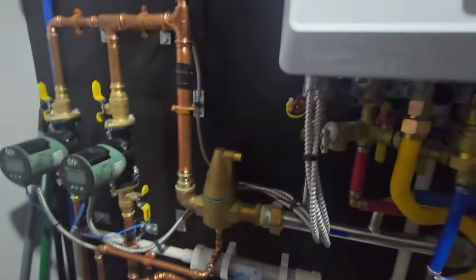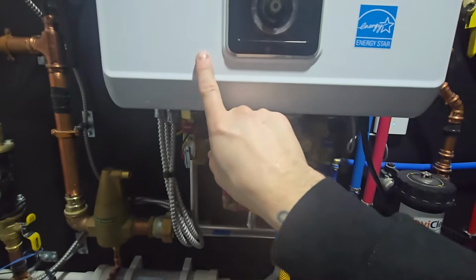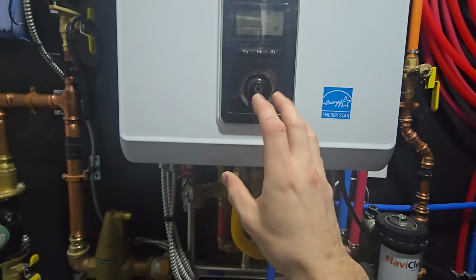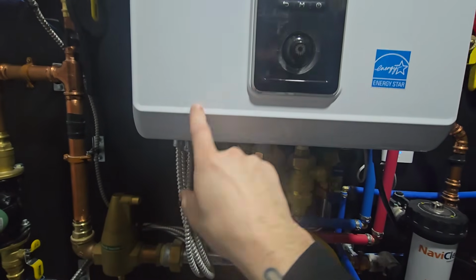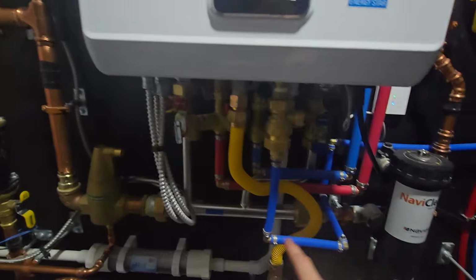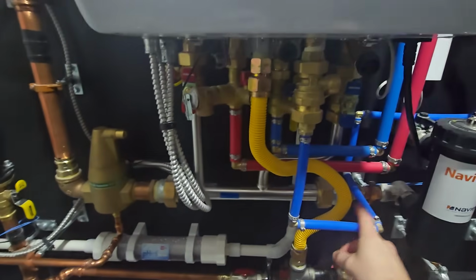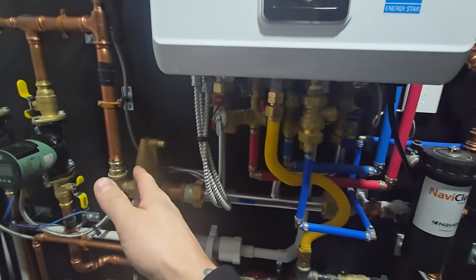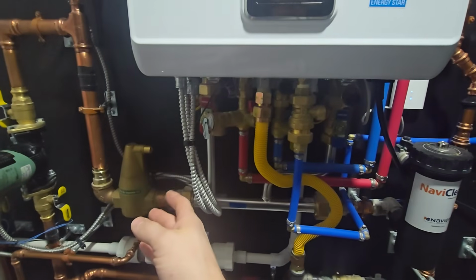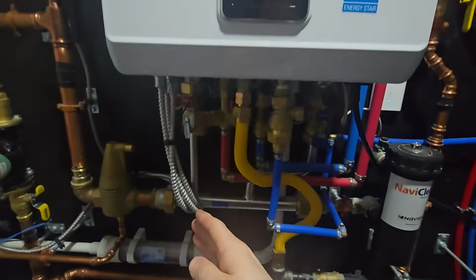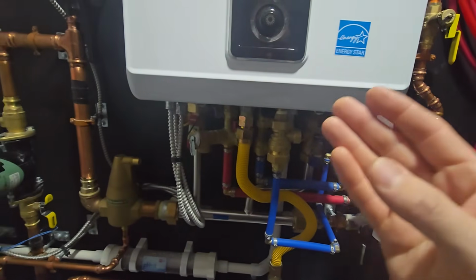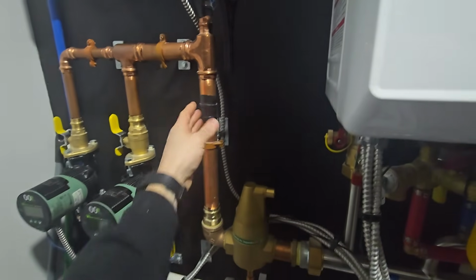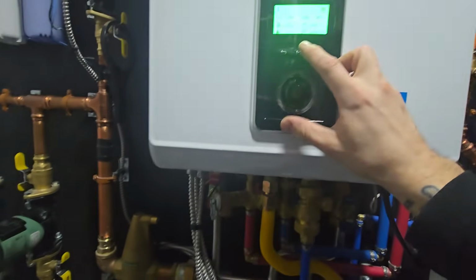Now what that does is typically the boiler would just be monitoring the water temperature that it's making. So if you set the boiler temperature to 120 degrees, it's going to read that there's 120 degrees going out. However, when you have the return water coming back into the manifold, it's going to be mixing with that 120 degrees. So you might knock that down to say 100, 115, but not 120 like the boiler is making. So the only way for the boiler to know what's really actually going to your zones is by putting an external sensor on the supply pipe. And then you will change that setting in the menu.